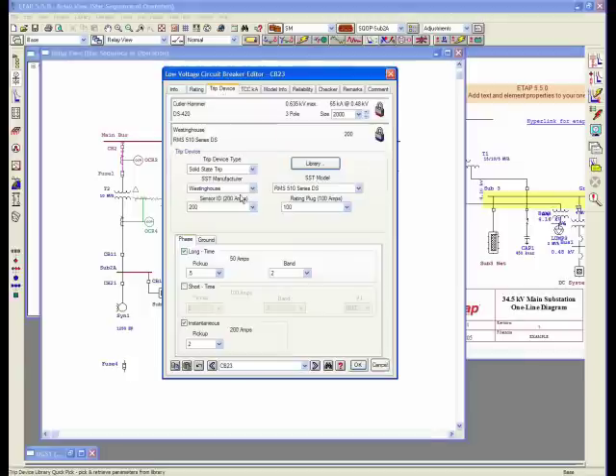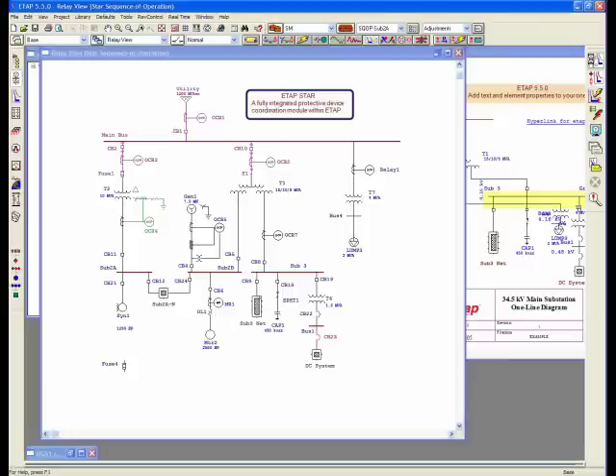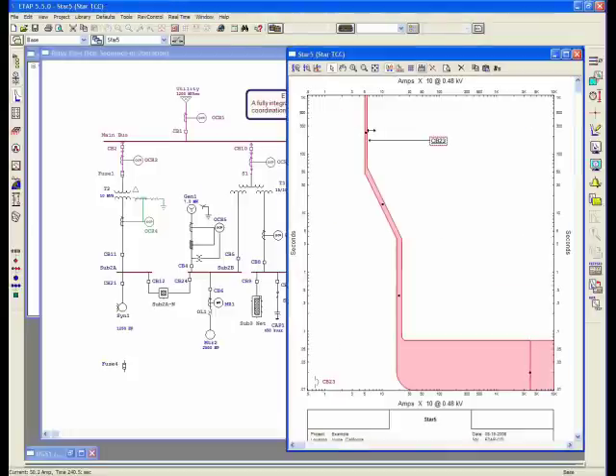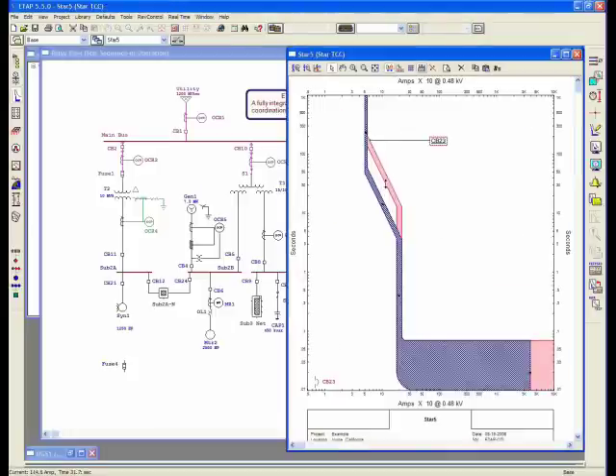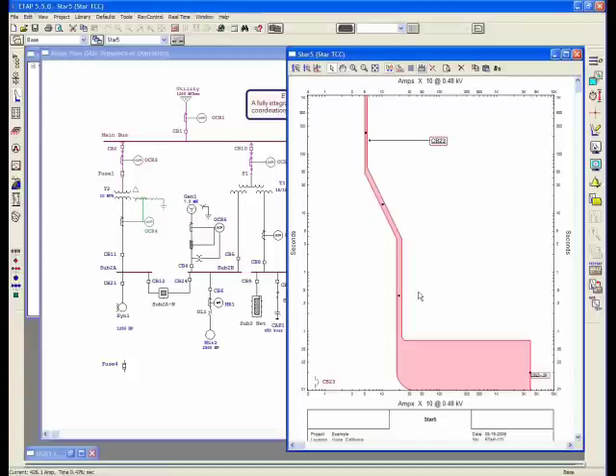This particular trip setting is a solid-state trip setting. It has sensors and plugs, and you have phase and ground functionality: long time, short time, instantaneous. Simply you can plot that and see how it looks. You have both the long time band, and in this case, since we don't have short time selected, this is my instantaneous. If I wanted to enable my short time, I could simply do that. It has both in and out functionality that I can enable, and now I have my long time, short time, and instantaneous. It's simple as enabling those features in your model and seeing the TCCs.